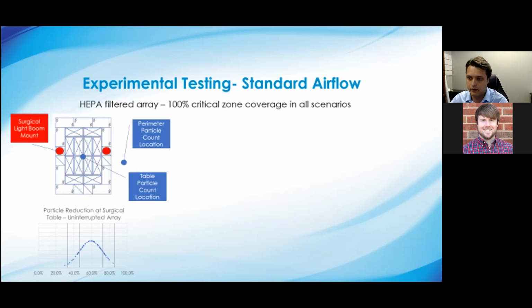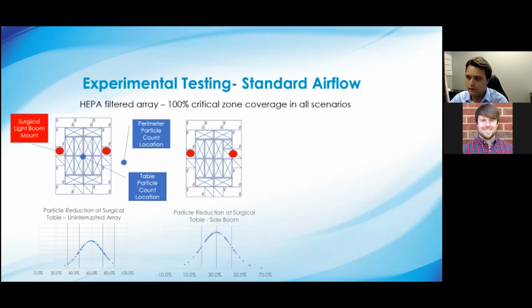Now, what happens if we play with the design a little bit? If we move one of those booms in just 2 feet, still not encroaching on that critical zone defined by ASHRAE, we still have 100% critical zone coverage. But just by moving that boom in 2 feet and having this area be inactive, you've cut the performance in half. Now you're only stopping 30% of particles that are in the room from reaching that patient.